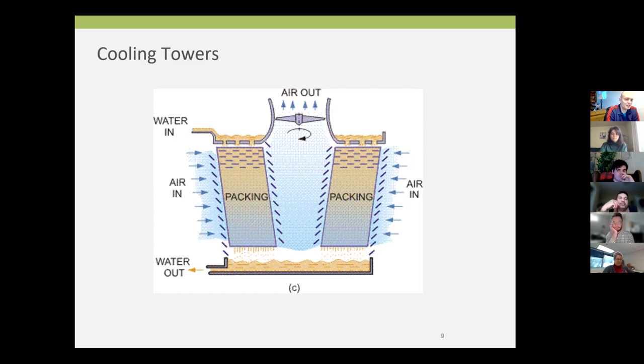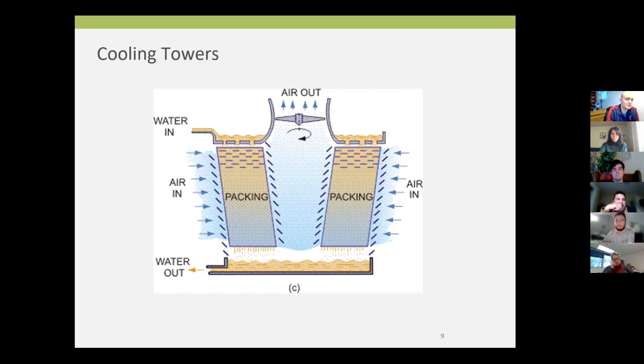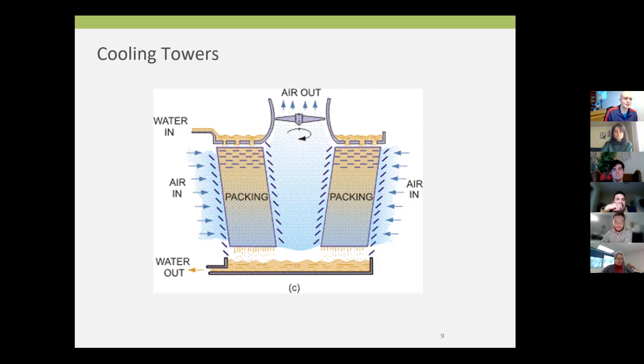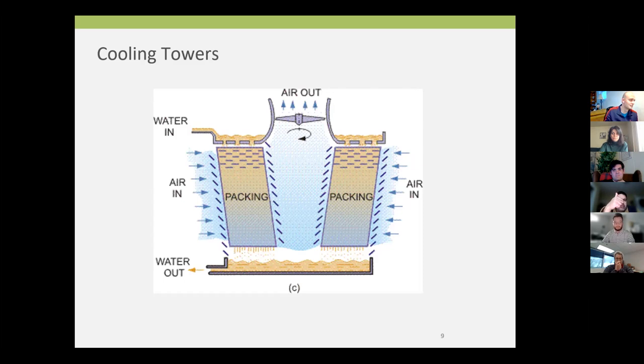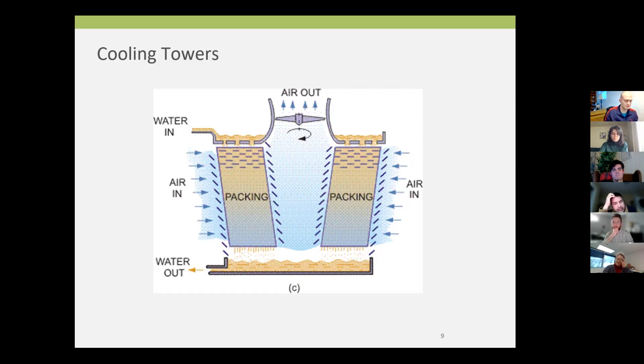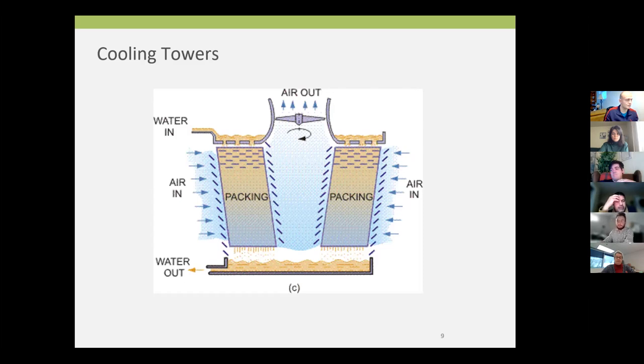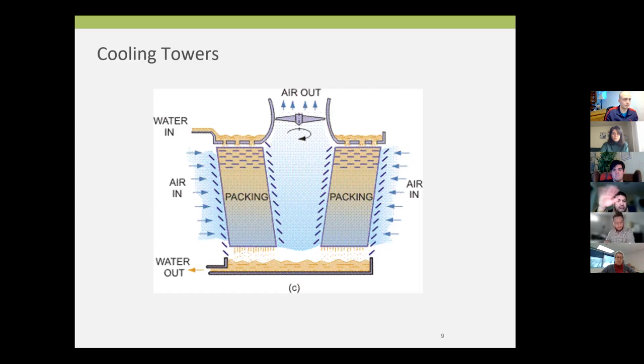We have a question in the chat. Does putting cooling towers in series provide colder water because the wet bulb temperature gets lower with each pass-through? No. Can someone else say why? I can answer that if Sonny wants to take a break for a second. Go ahead, Andrew. The air that you're using for each one is going to be the same temperature each time because you're pulling it from outside. The only way that you would end up with colder water is if for some reason your first one wasn't working properly and then you put it through one that was. But the air that's coming in is going to be the same temperature. So, you have the same wet bulb temperature for each because you start with the same dry bulb and the same humidity. It's coming from the same atmosphere. And your wet bulb is going to change maybe depending on location or altitude or things like that. Not because of a smaller configuration. And your wet bulb typically around a particular location is not going to change within five feet. So, wet bulb at the University of Utah campus is the same at the football stadium as it is at the Huntsman Cancer Institute.